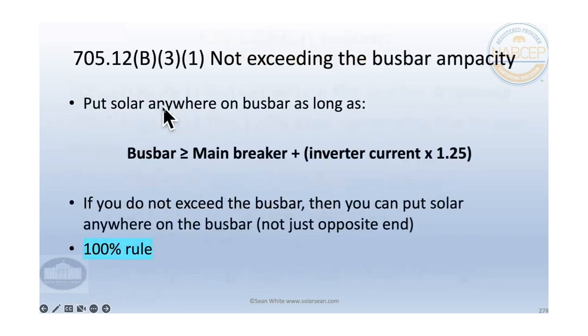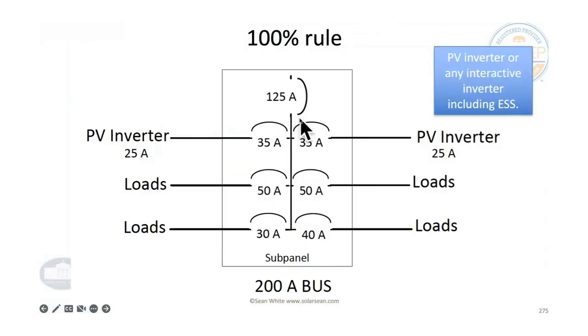And so let's look at the pictures. The 100% rule is you don't have to put your inverters at the opposite end of the bus bar, like the famous 120% rule. You can put them wherever you want, but you can't exceed the rating of the bus bar when you add up the main breaker plus 125% of inverter current. So this is showing the inverters right next to the main breaker. And that's okay, because when we add all these together, it's obviously less than 200 amps.